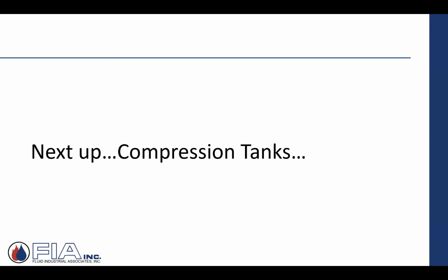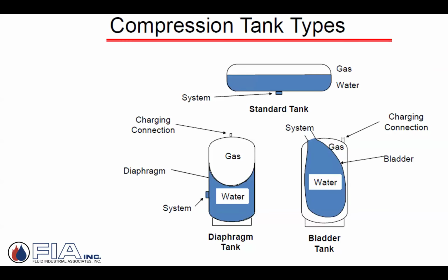Next component, if you will, that we're going to come up against, compression tanks, expansion tanks. They have a bunch of different terms, if you will. Again, line drawings, but what we're showing here is 3 different technologies. The old style, if you will, a steel, a standard tank, they might call it, or a standard compression tank. I'm going to show you guys what this is and make you aware of it. You're probably never in your career ever going to specify something like this. It's going to be down here, either a diaphragm style or a bladder. But every now and then out in the field, you might bump up against it, you just want, education-wise, to be aware of what that technology was.